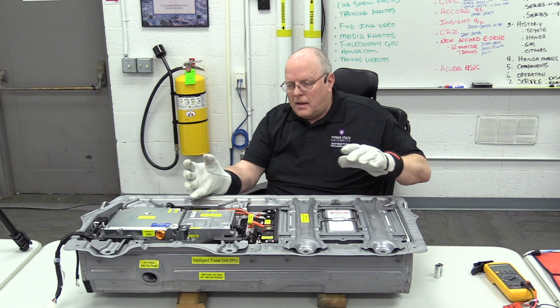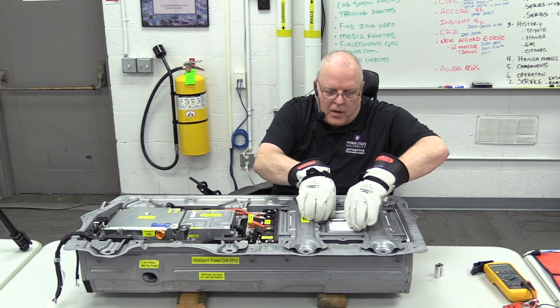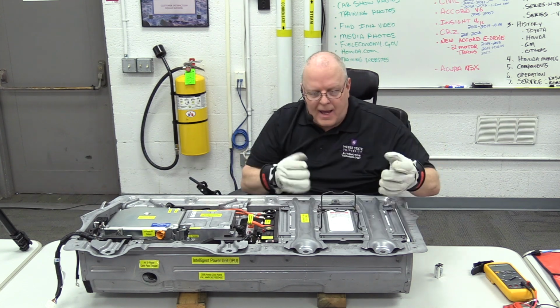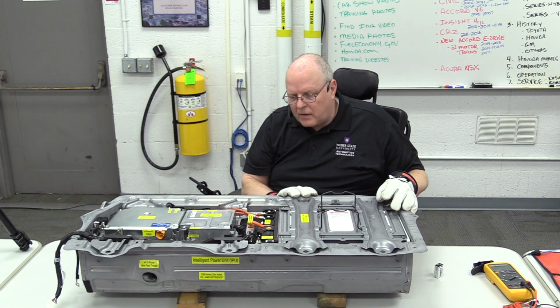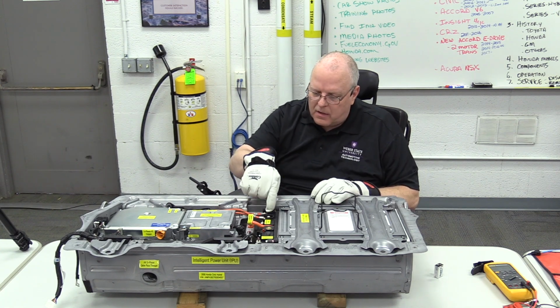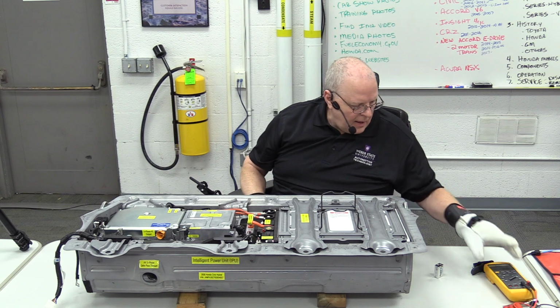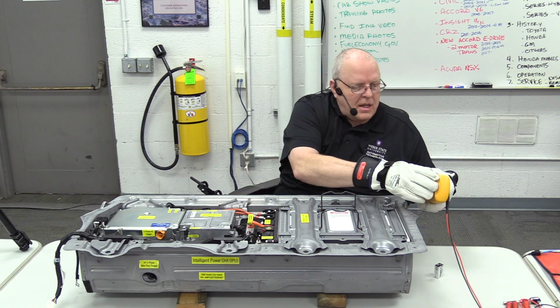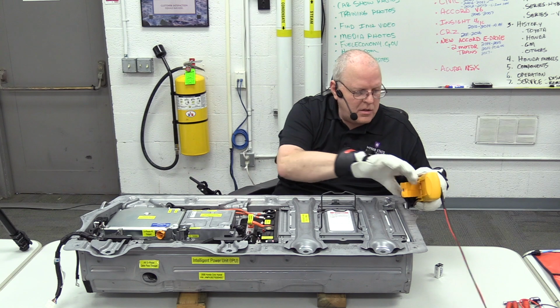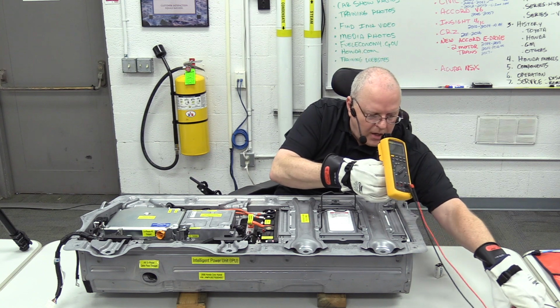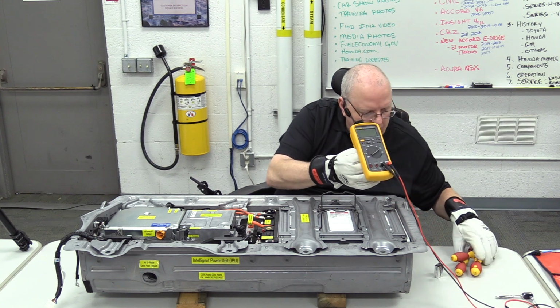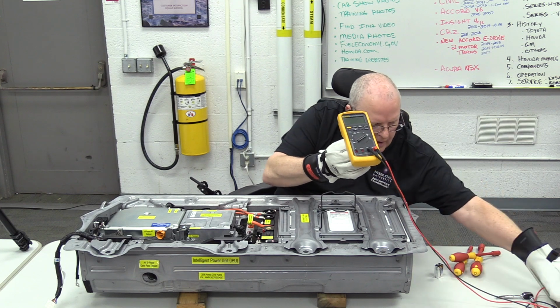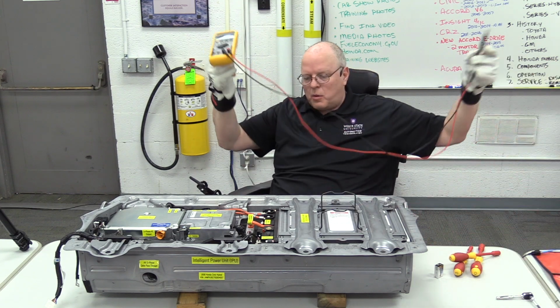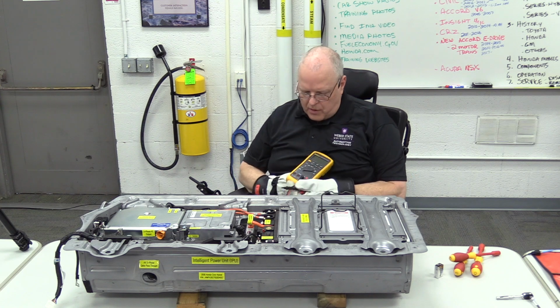Now, the battery has some lift out handles right here, but we can't lift it out without disconnecting it first. To disconnect that, even though the power switch is off, we always want to check to see if we have a voltage on those cables before we put a wrench on there.